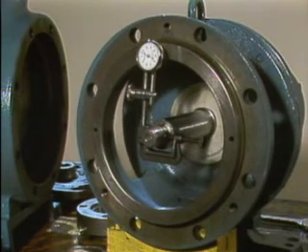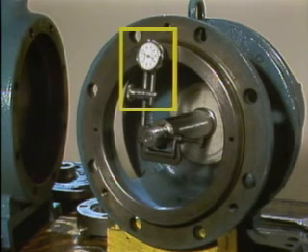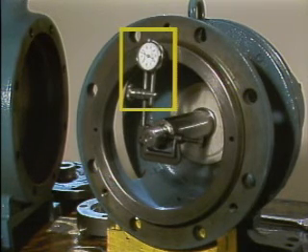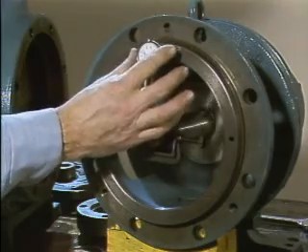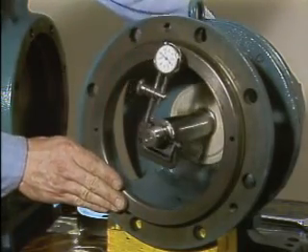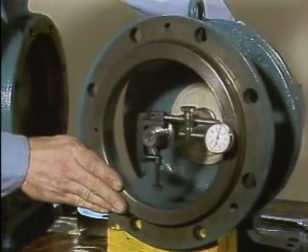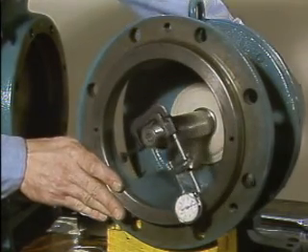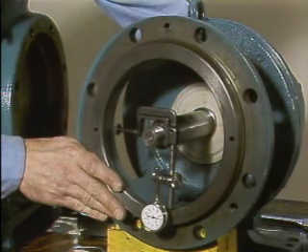Another important check using a dial indicator is checking the machined surface of the pump frame to see if it's perpendicular to the shaft. The pump backplate, which also forms the stuffing box where the mechanical seal components will fit, mounts directly to this frame, so the frame must be perpendicular to the shaft to prevent misalignment and seal damage. The frame is checked by mounting a dial indicator on the shaft so that the stem touches the machined surface of the frame. The dial indicator is zeroed, and a mark is made at the starting position. Then the shaft is rotated. 4 readings are taken at 90 degrees apart. If the frame and the shaft are perpendicular, the 4 readings should be the same.